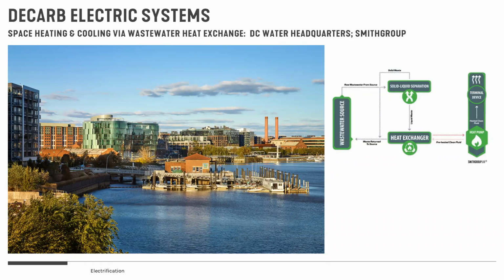We had been doing research in wastewater heat exchanger systems, and this is the first building in the United States that uses wastewater heat pumps to do all the heating and cooling for the building. There's no cooling tower on this project, no big equipment. It's actually a pretty small heat pump in the basement that provides all the heating and cooling by extracting waste from that sewer line, macerating it, running it through a heat exchanger, and then returning it to the sewer.